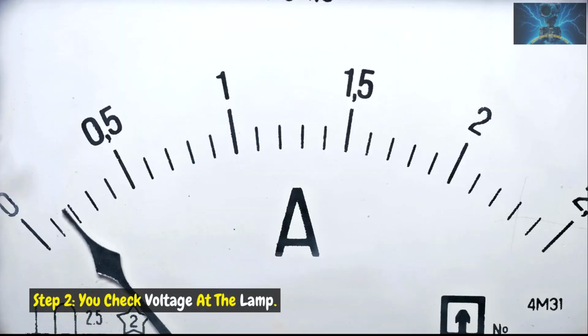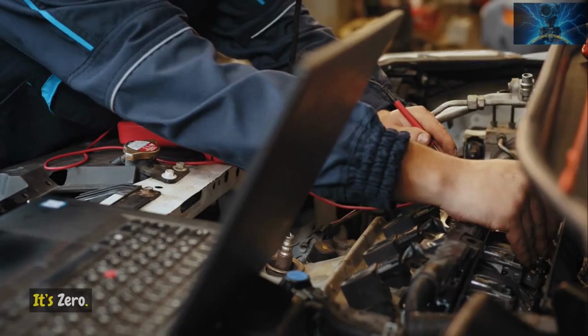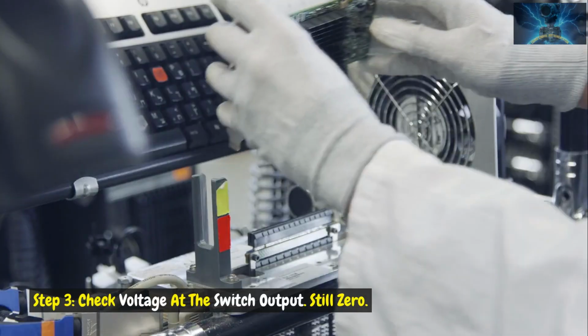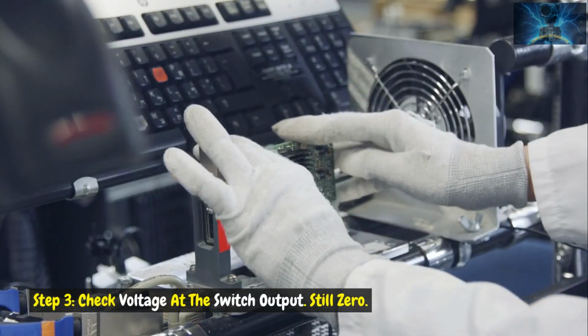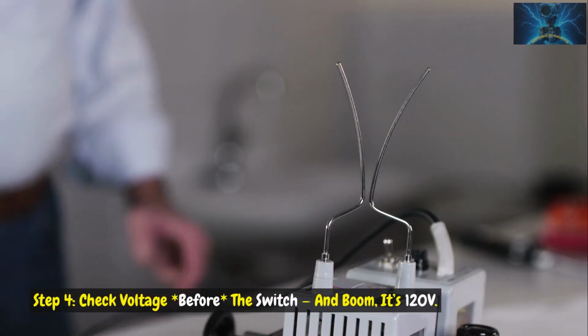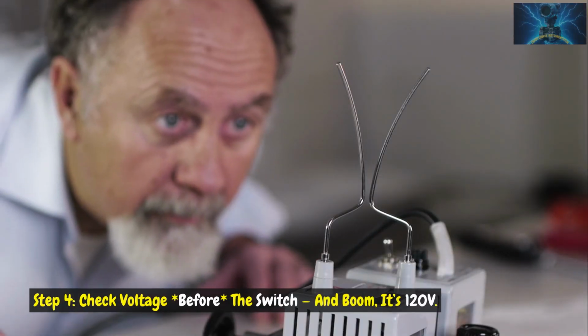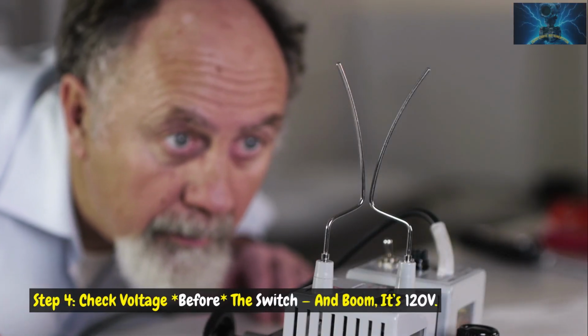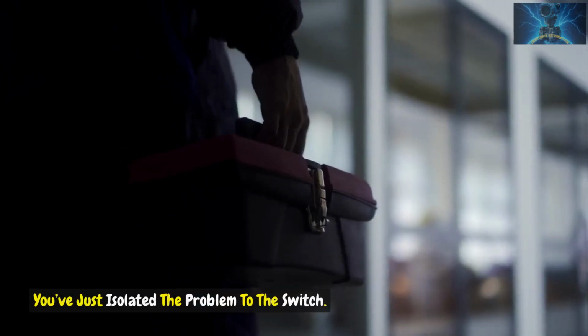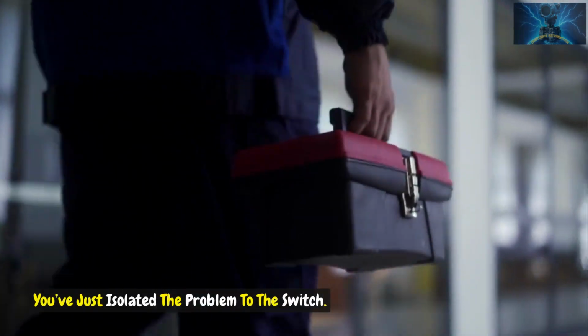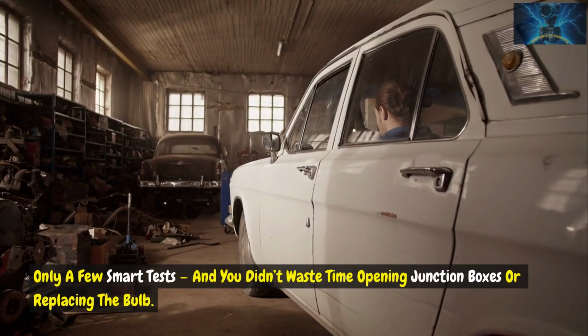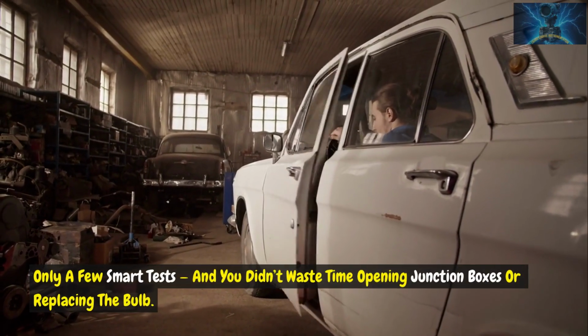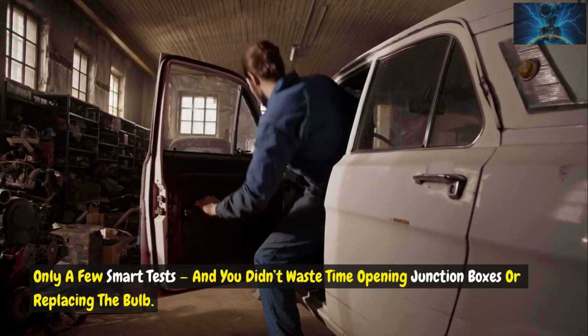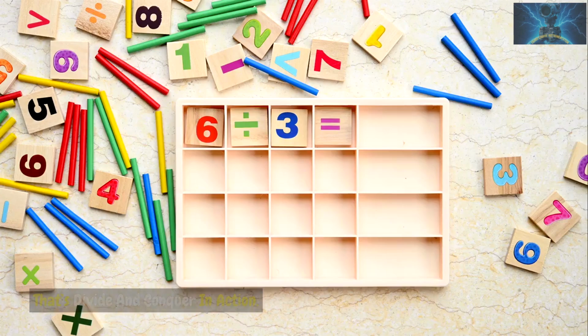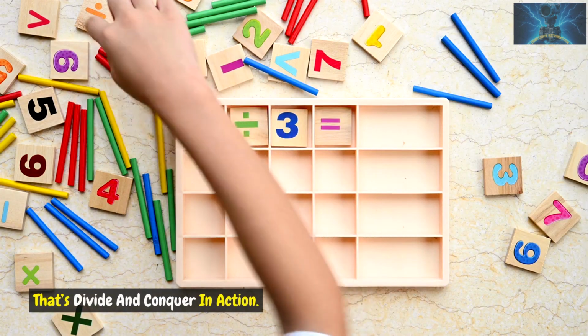Step 2, you check voltage at the lamp. It's 0. Step 3, check voltage at the switch output. Still 0. Step 4, check voltage before the switch, and boom, it's 120 V. You've just isolated the problem to the switch. Only a few smart tests, and you didn't waste time opening junction boxes or replacing the bulb. That's divide and conquer in action.